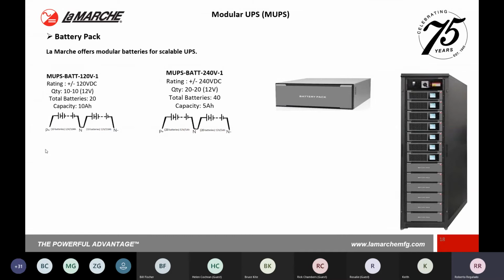The special thing here is that you actually have two strings. If you were to use an external battery for the MUPS, you'd need a 240 volt battery or two 120 volt DC batteries for this one, and two 240 volt batteries for the other. There's a 120 volt battery connected between positive and neutral, and another 120 volt battery connected between negative and neutral. That combination is technically 240 volts DC, but it's split.